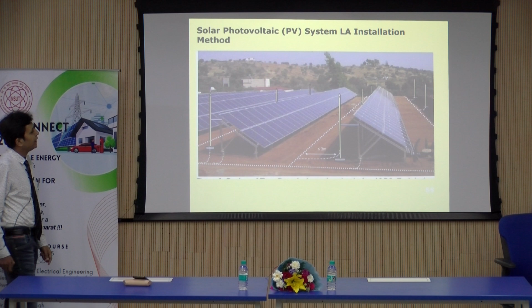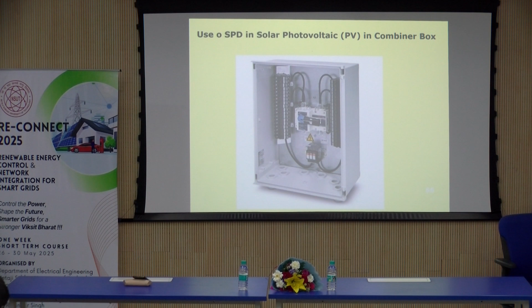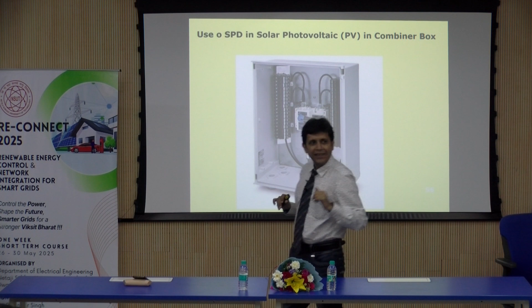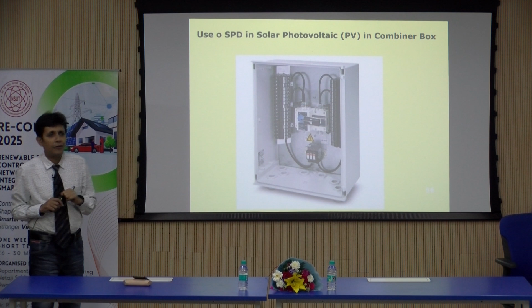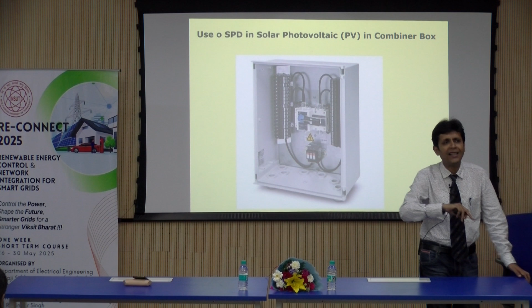SPD, surge protection devices. We have talked about lightning. Lightning may strike on your building. It may damage your solar PV. And finally your solar PV is connected to your load inside the building. That lightning comes for microseconds, for a very short duration, and SPD helps you to save the equipment you are using in the building, and that is to be provided on the AC side and the DC side. Next one.